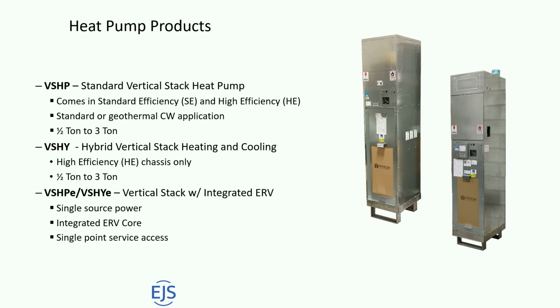And what we care about most today is the efficiency in heating season, because it's really the temperature of the water that changes in a conventional system versus a geothermal system. We're getting that colder water, so the units are going to operate at a much colder water temperature. So your COP, your performance, your efficiency in heating is worse in a geothermal system. The VSHY is the hybrid system. So we talked a little bit about hybrid systems where we're using a boiler of some sort that's going to inject heat into a hybrid loop because we can't get enough ground area for a geothermal 100%.